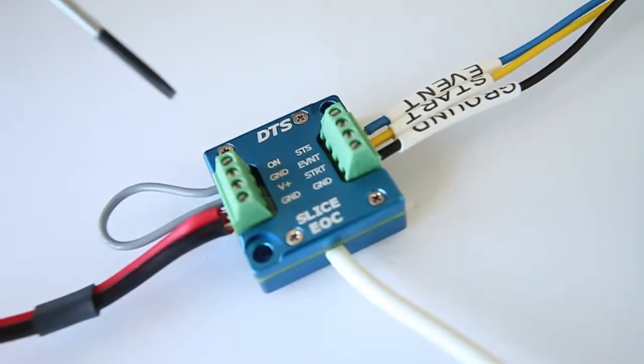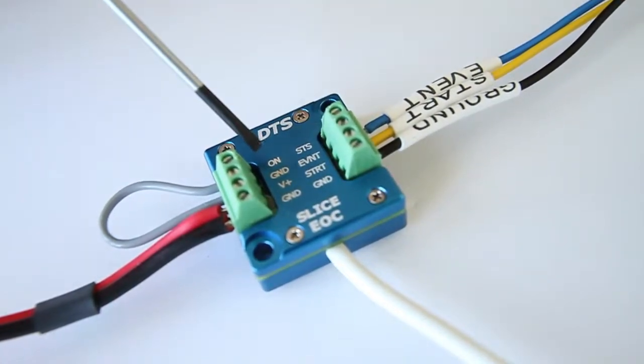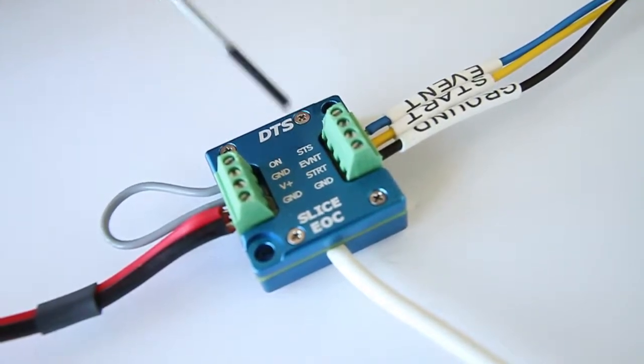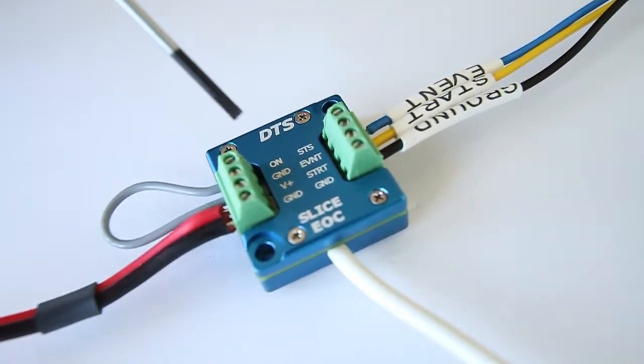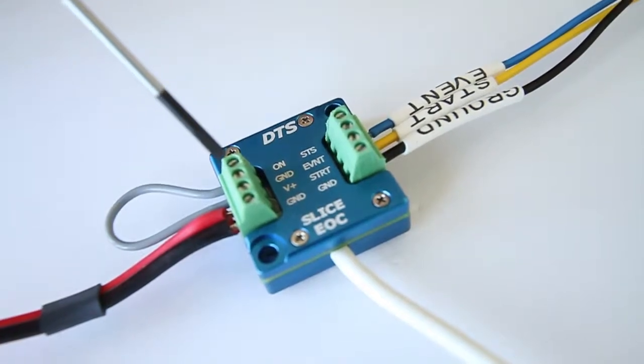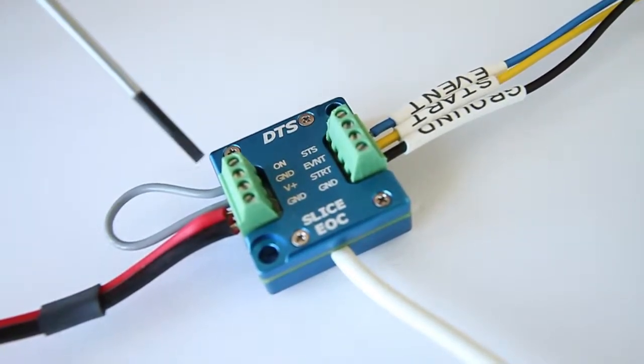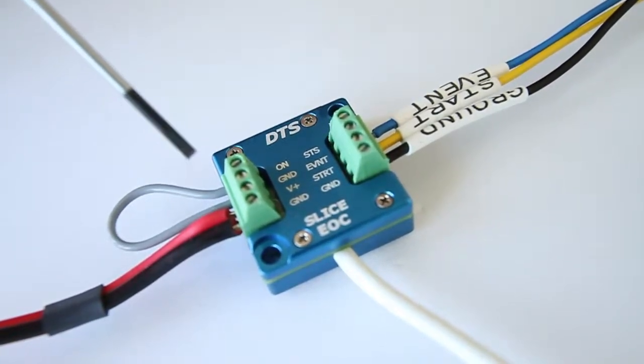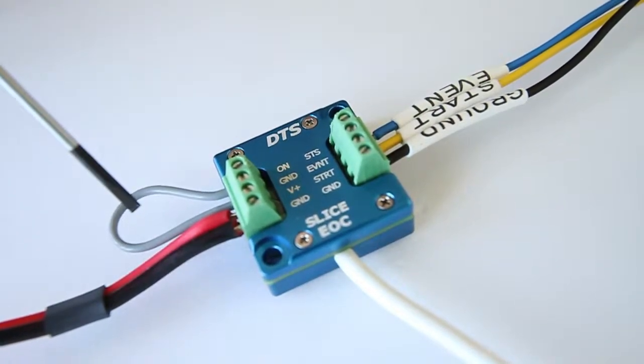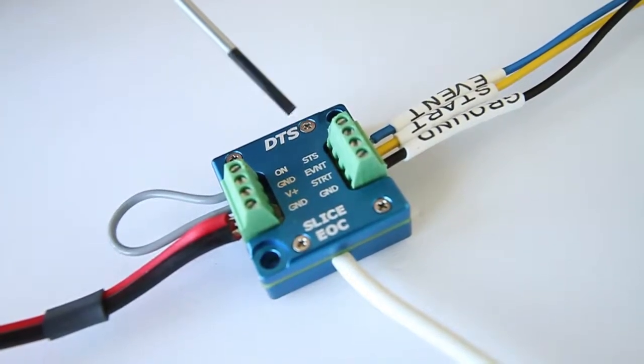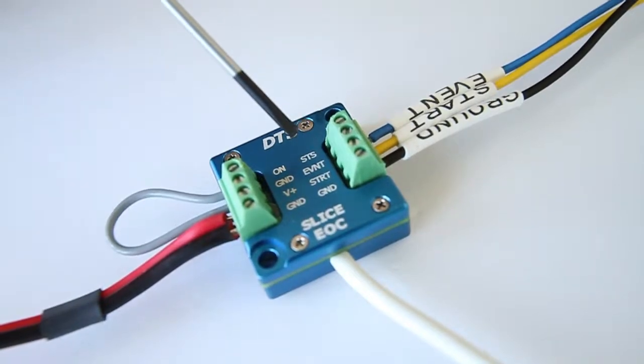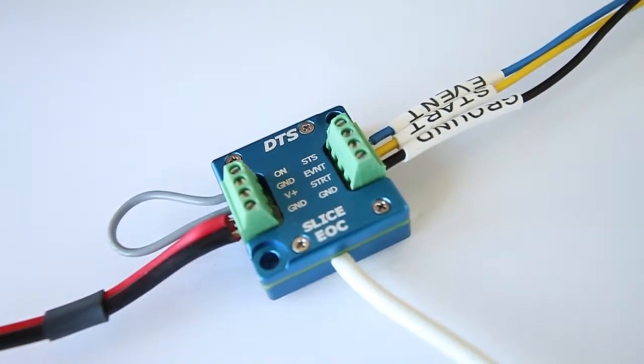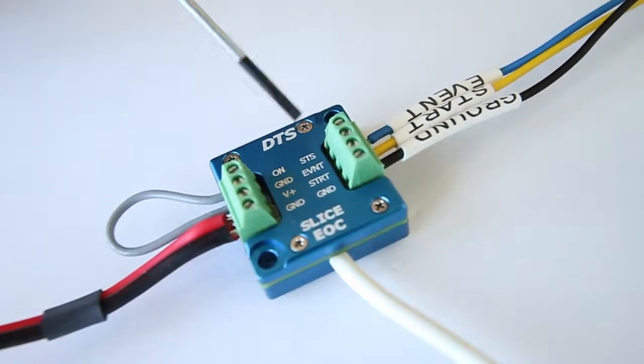The end-of-chain cable also has connections labeled on and STS or status. When you connect on to ground, it turns on the system. You can also use these signals to connect a remote power control switch. Status is there to give you an indication when the system is ready and recording and everything is okay.